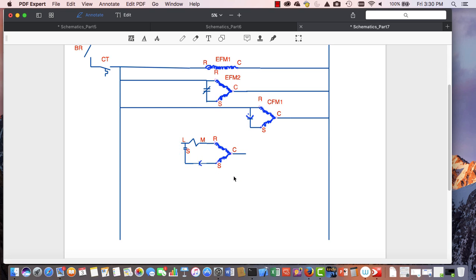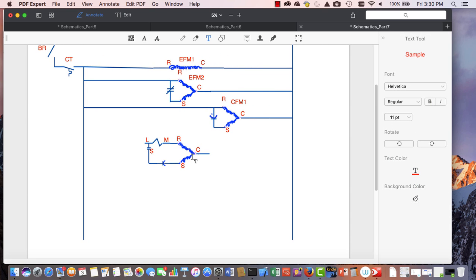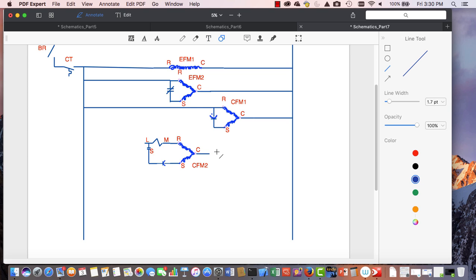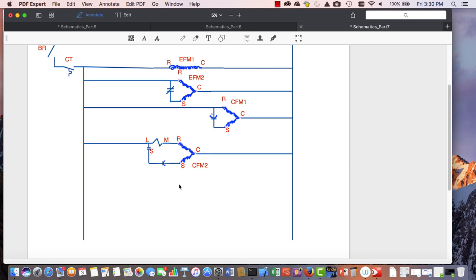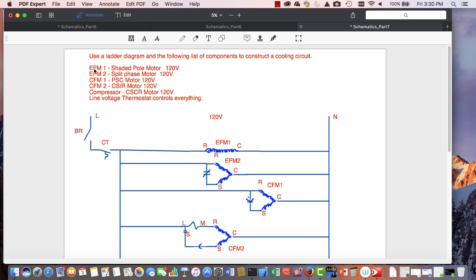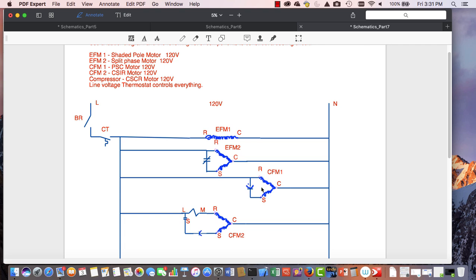Okay, so CFM2, I'm just going to label this before I draw the lines in, just so that I don't lose sight of the fact I got to label it. Okay, so now I got to connect my common to neutral. Okay, so that's CFM2. So going back up to our diagram, EFM1 is my shaded pole, single winding. EFM2 is my split phase, start and run winding. However, it has a start component, centrifugal switch in this case, to take out that start winding. PSC motor has a run capacitor that's always in the circuit.